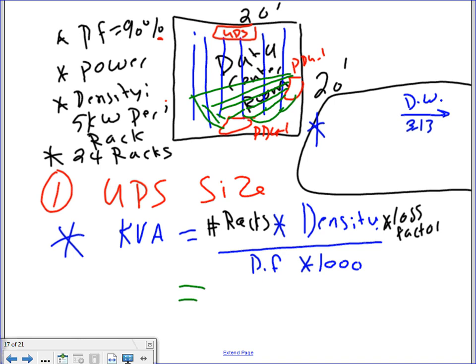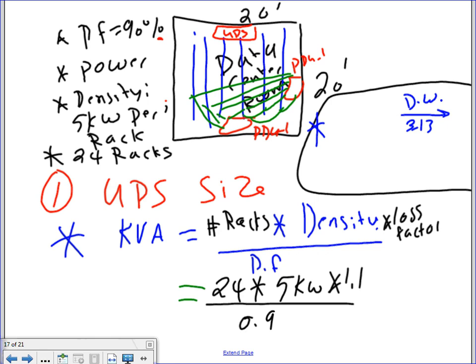Now I don't have a calculation for this, so you guys are going to help me for a little bit. So let's start. The number of racks, I have 24 racks. By the way, this is our project. This information is pulled directly from our project, so the sizes you come up with right now, all the numbers, you're going to be putting in your project. So 24 racks multiplied by the density, which is what? Per rack, 5 kW. Because we have 5 kW, I'm going to get rid of the 1,000 here. Can you guys get rid of the 1,000? Everybody get that? Multiplied by the losses, 1.1, divided by a power factor of 0.9. I do not have the answer for this, so I need one of my best friends to give me the answer. 2 people, please.